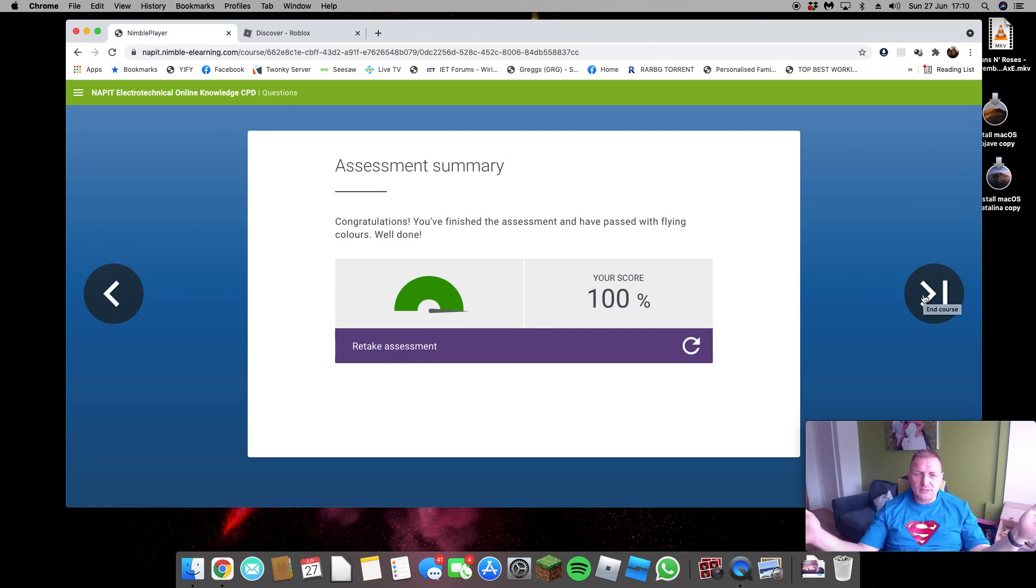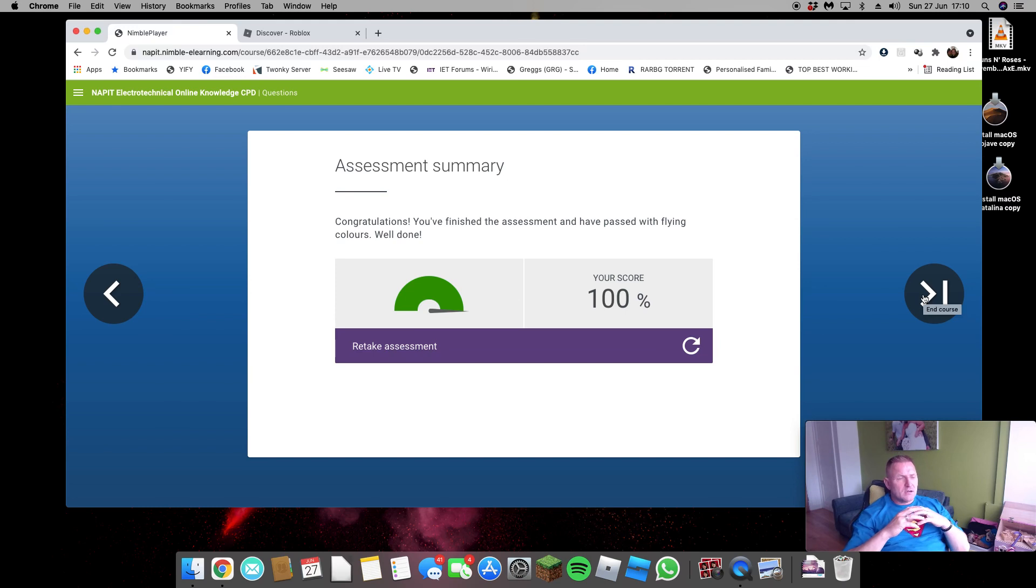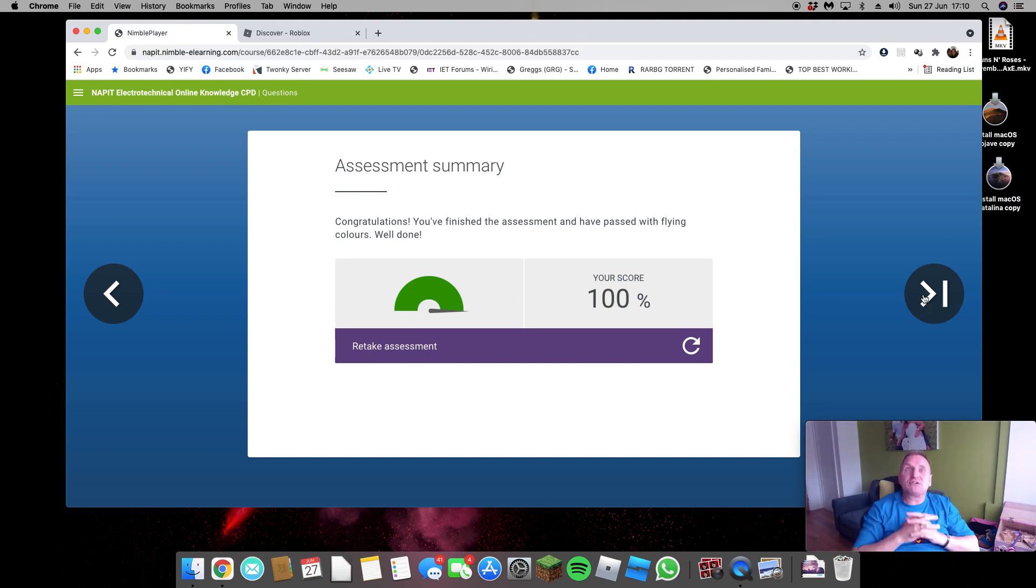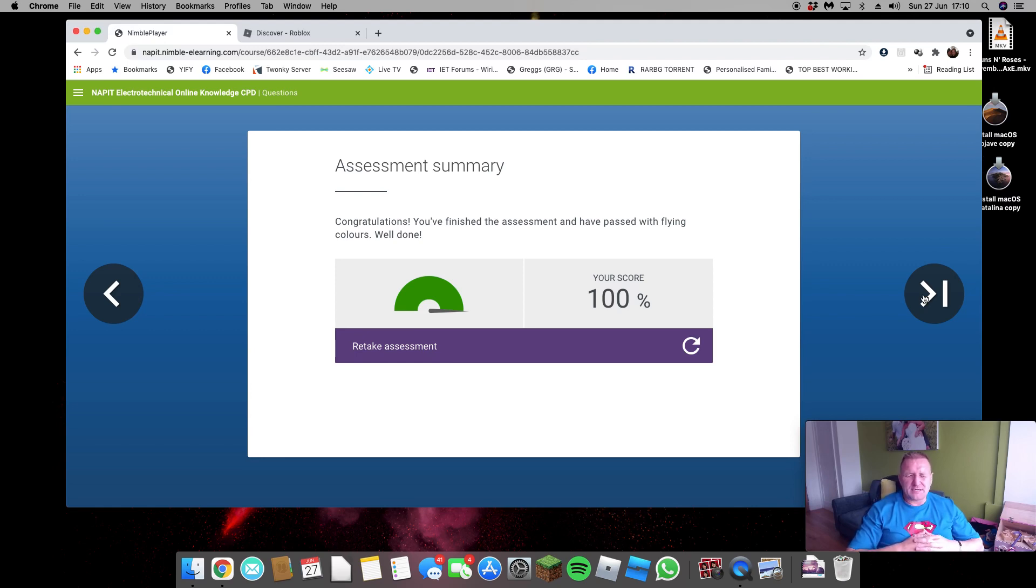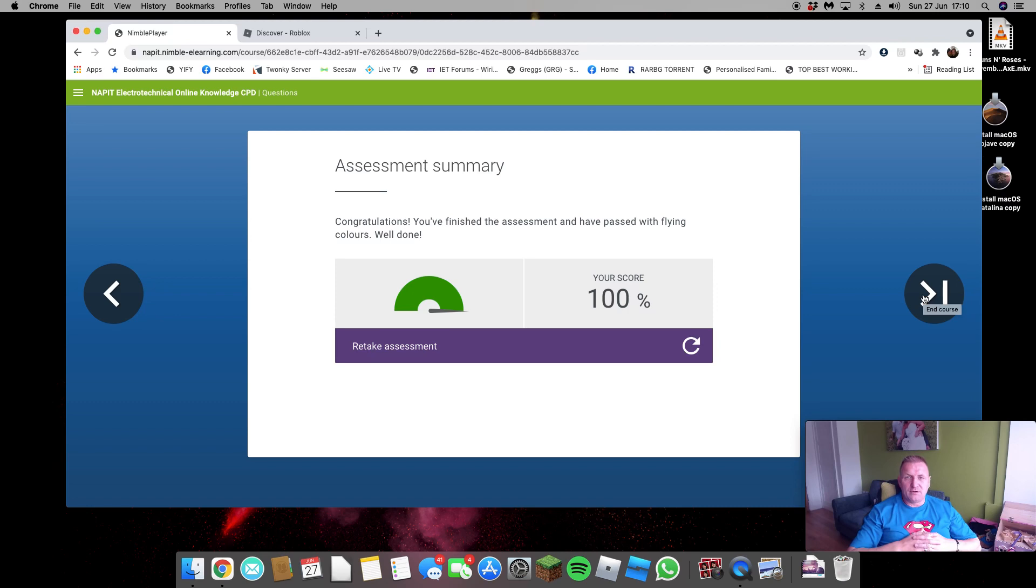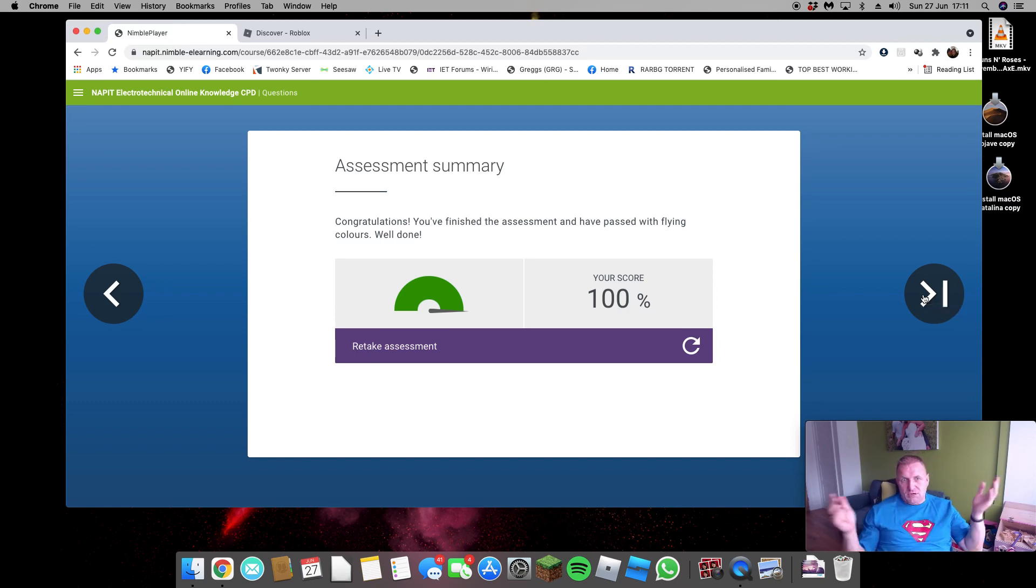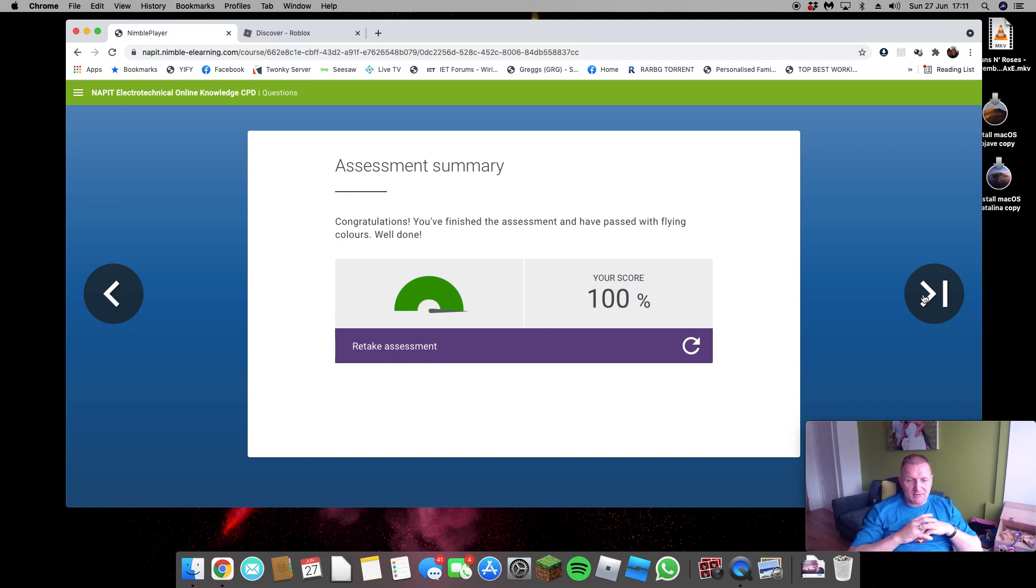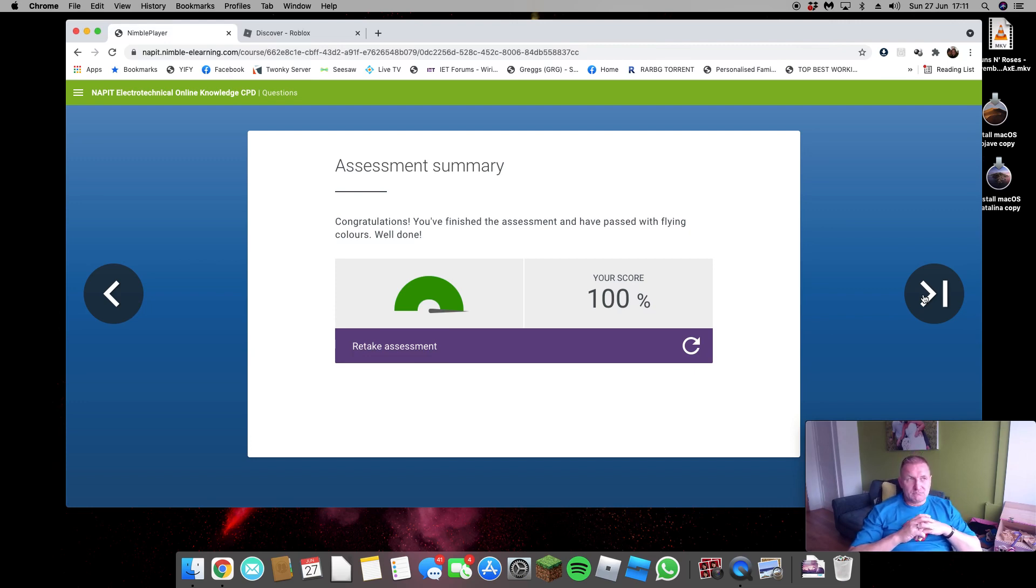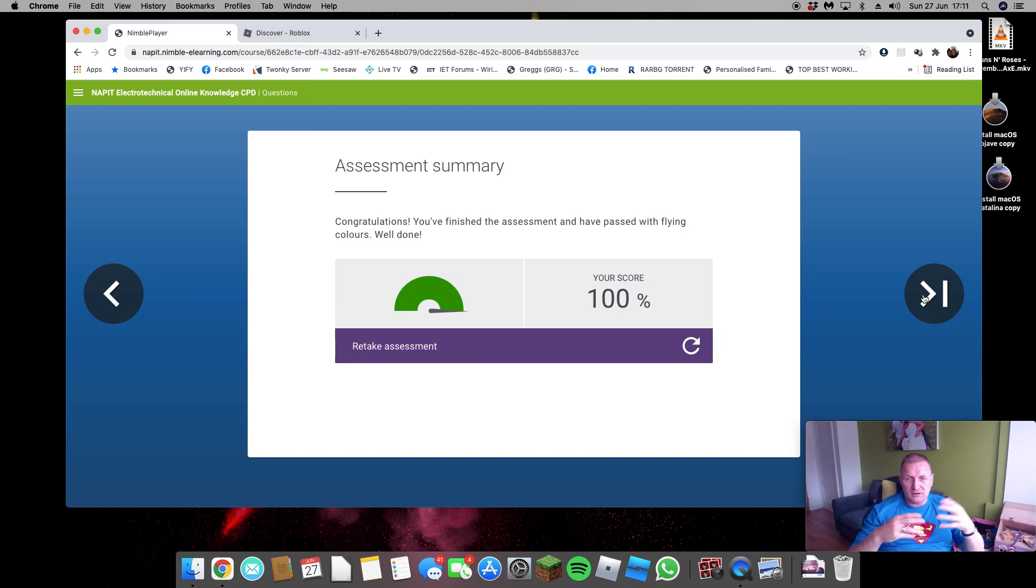And 100%, so there we go, that's the assessment. Yeah, the surge protection one was a bit of a dodgy question. They must, I'm just thinking, I installed two types of SPDs: one is in series and the other is in parallel. Now the Lewden are in series and the Wylex are in parallel. So who knows what they're choosing? Go for the Wylex route if you're asked that question. So you've got your incoming tails and it's running parallel with the cutout, with the cutout fuse, which is your protective device. Lewden again got a protective device but running in series. So there we go, 100%.